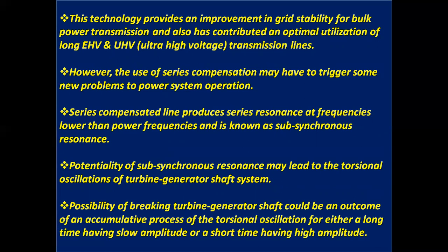However, the use of series compensation may trigger some new problems in power system operation. A series compensated line produces series resonance at frequencies lower than power frequencies, known as sub-synchronous resonance. The potential of sub-synchronous resonance may lead to torsional oscillations of the turbine generator shaft system. The possibility of breaking the turbine generator shaft could be an outcome of an accumulative process of the torsional oscillation, either over a long time with slow amplitude or a short time with high amplitude.